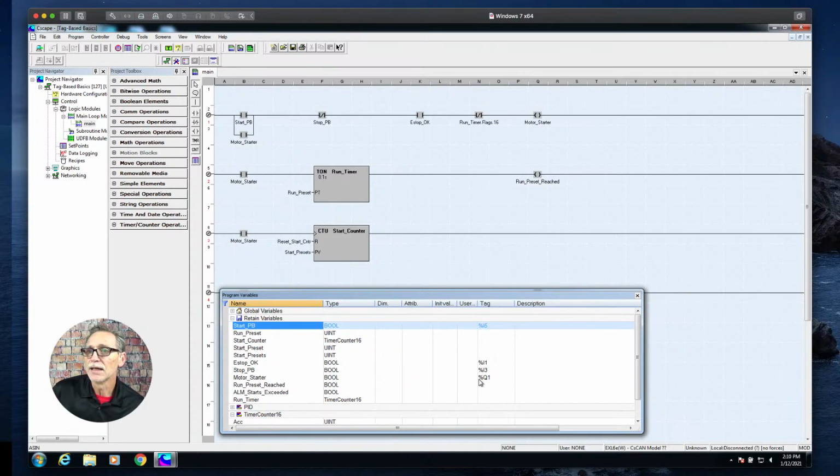Effectively then, there are other situations where you need to map variables to specific locations. Another example might be if you're going to share a variable outside of the application, maybe over Modbus or Modbus TCP protocol. Now, Modbus protocol is definitely a memory mapped or register-based protocol. So in that scenario, if you want these variables to be accessible outside over Modbus, for instance, and in a typical application, it's only a small subset of your total variables, then you would want to map those as well. But again, we're not going to cover that directly in this particular video.